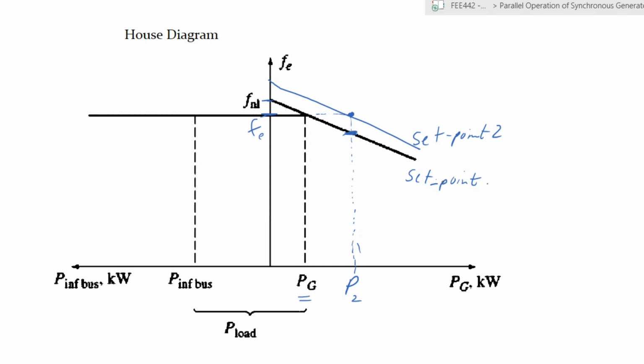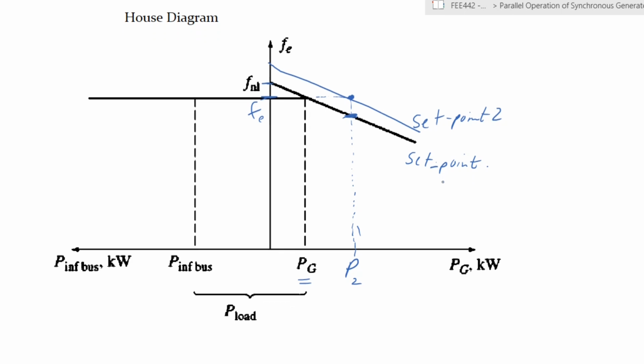And the same thing would apply in terms of reactive power. You would have to match the terminal voltage of the infinite bus bar to the reactive power that you need to supply. So now let's go a bit deeper into some of the conditions that will be faced when you're trying to connect a generator into an infinite bus. First, what happens when your governor set points change without a change in the voltage or the field regulator? Remember, you have both of them on the same machine.